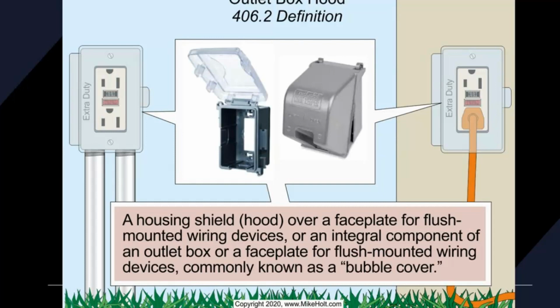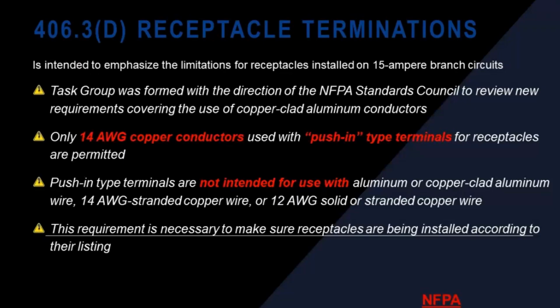Okay. A housing, shield, or hood over a faceplate for a flush-mounted wiring device, or an integral component of an outlet box, or a faceplate for flush-mounted wiring devices commonly known as a bubble cover, is required per 406.2. 406.3(D) covers receptacle terminations. This is a new code change. This is new in the 2023.